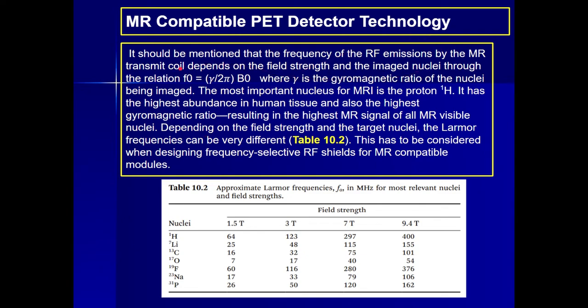RF emission by the MR transmit coils depends on the field strength and the imaged nuclei through the relation f0 = (gamma / 2 pi) times B0, where gamma is the gyromagnetic ratio of the nuclei being imaged. The most important nucleus for MRI is the proton. It has the highest abundance in human tissue and also the highest gyromagnetic ratio, resulting in the highest MR signal of all MR visible nuclei. Depending on the field strength and the target nuclei, the Larmor frequencies can be very different. This has to be considered when designing the frequency selective RF shield for MR compatible modules.